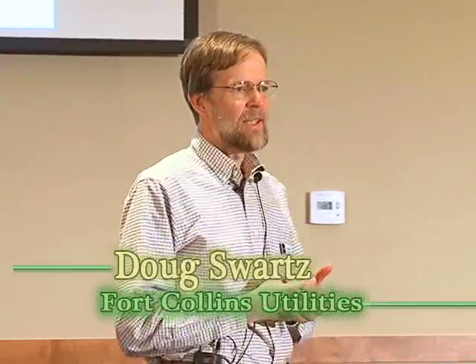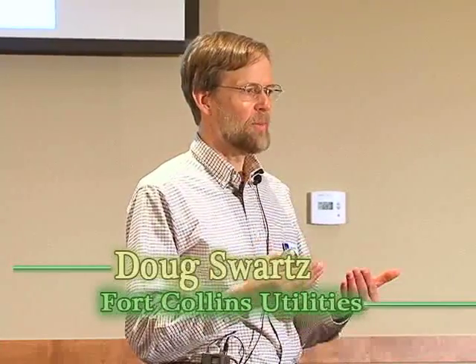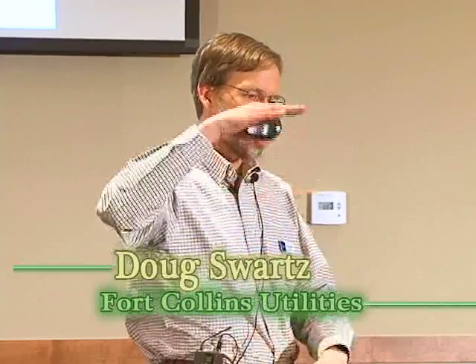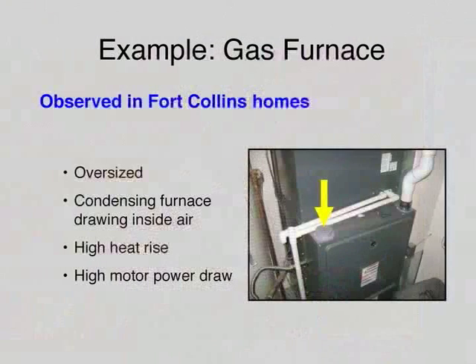We see furnaces that don't have enough airflow because they're poorly matched to the ductwork. When you don't get enough airflow, you get a high heat rise—the increase in temperature as the air goes through the furnace. Again, you're throwing away efficiency and shortening equipment lifetime when you have high heat rise.